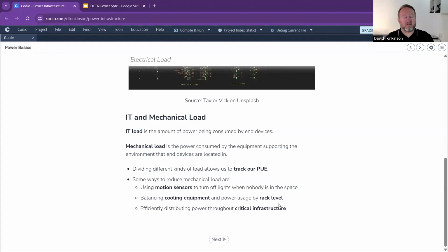So I can then simply say, actually, in my data center, I'm likely to have this many of those particular racks available. And that gives me a rough balance of what I should have. And then what you tend to do is you double it. You work with some fantastic numbers like that. A lot of it is guesstimates. You double it because you're working for the future and not for what you currently think you're going to put in. And that's how you work it. So there's some good maths you can apply to it.